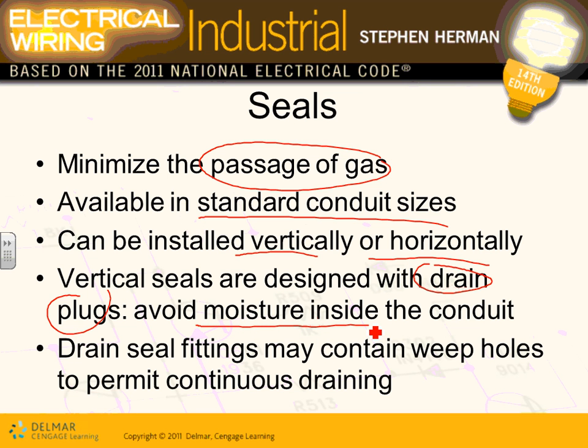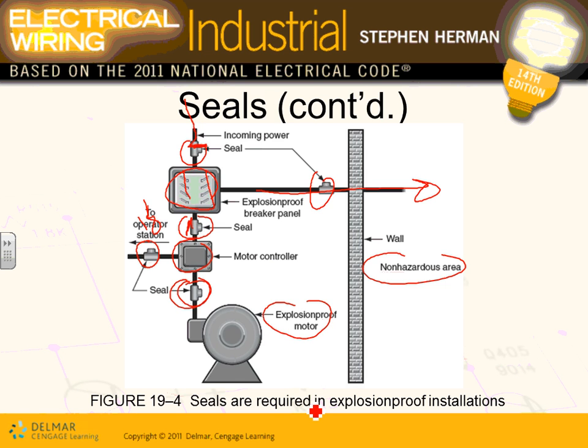Drain seal fittings may contain weep holes. Some of them have weep holes to permit continuous draining. So right here, gentlemen, in this area, when you have a vertical, there will be a little bit of weep holes here. So if there's accumulated water because of condensation, it will allow it to seep and get out. It wouldn't allow the gas to get in, but it will allow the water to move out. It's like a valve. Any comments, guys?